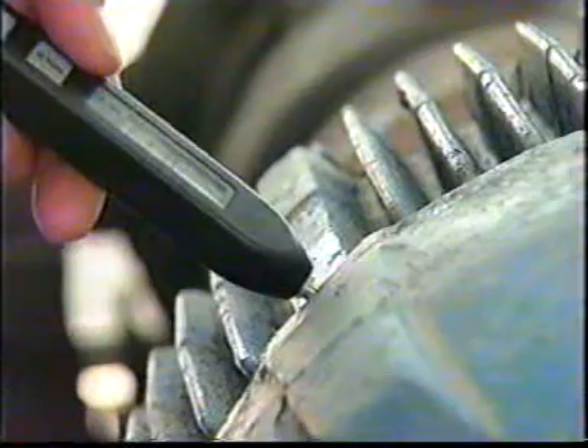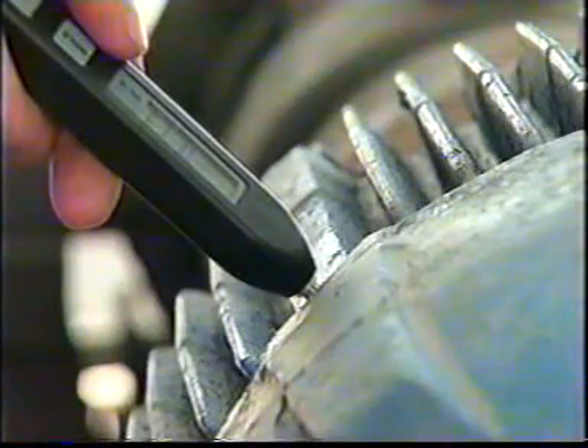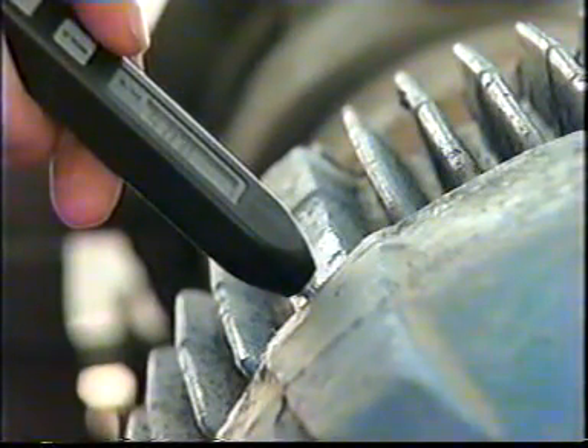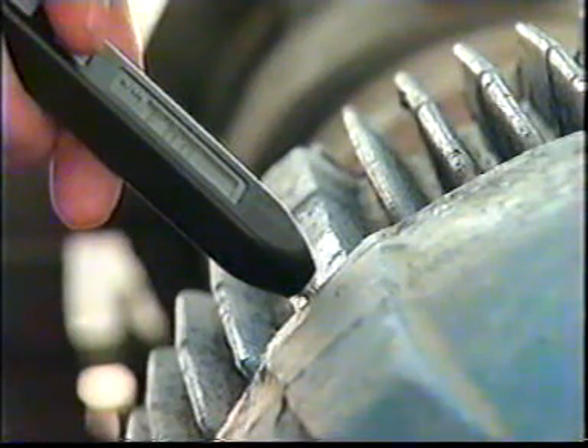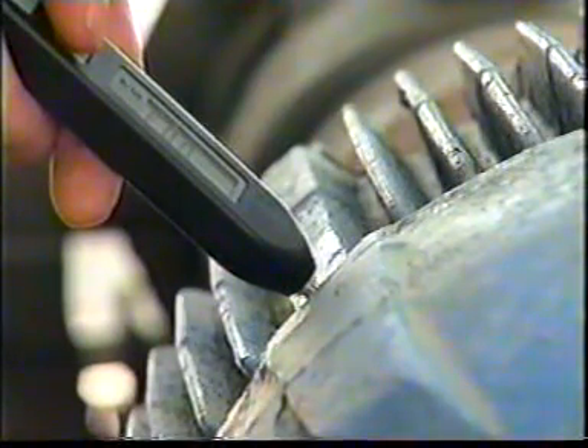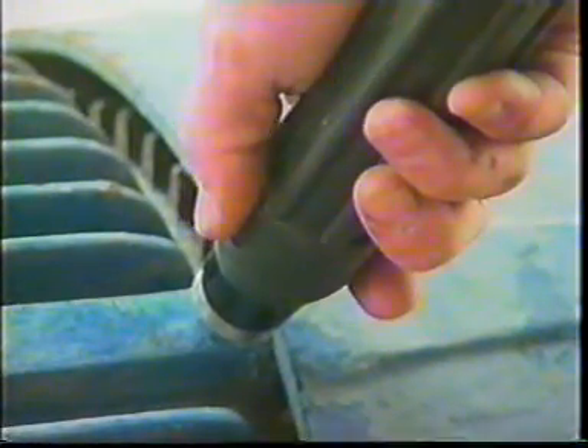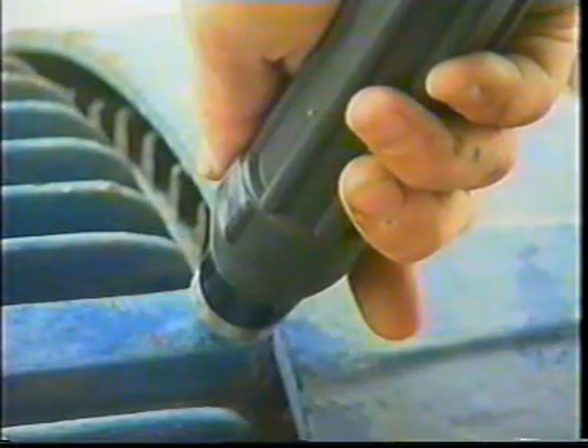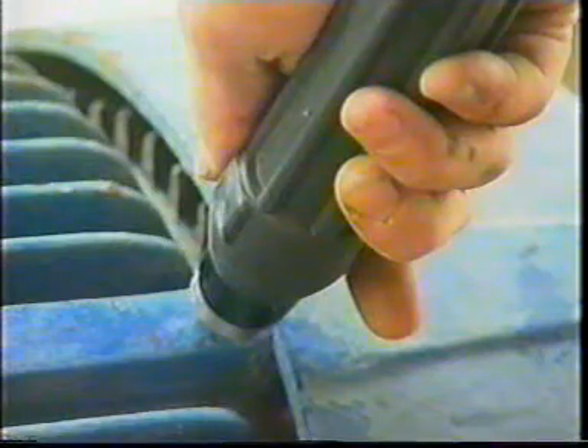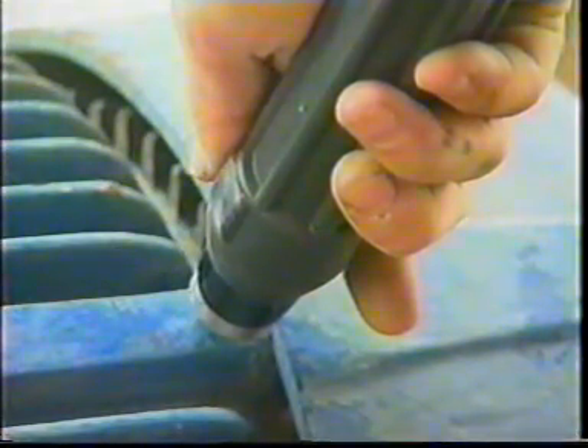The sensor needs to be perpendicular to the machine's surface. Tilting the probe slightly could cause significant differences in vibration amplitude readings. When using a handheld probe, be sure to keep constant pressure to maintain contact on the machine's surface. Variations in contact pressure can also produce errors in amplitude readings. The sensor needs to make full contact with the machine to get the best and most accurate response.